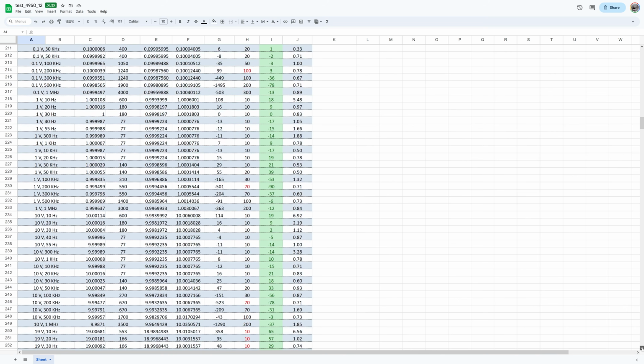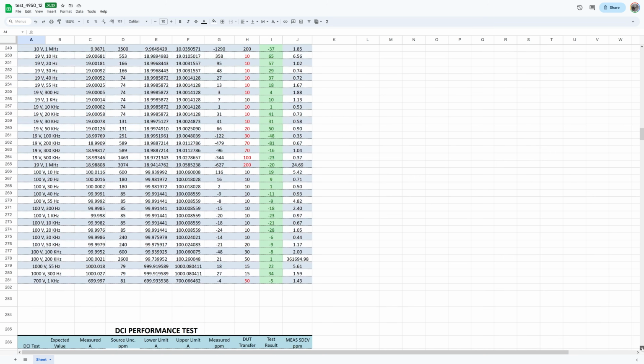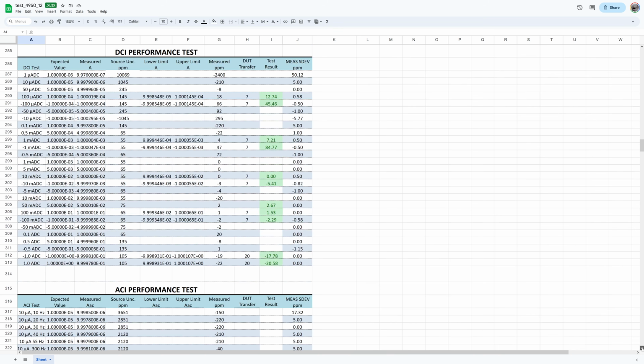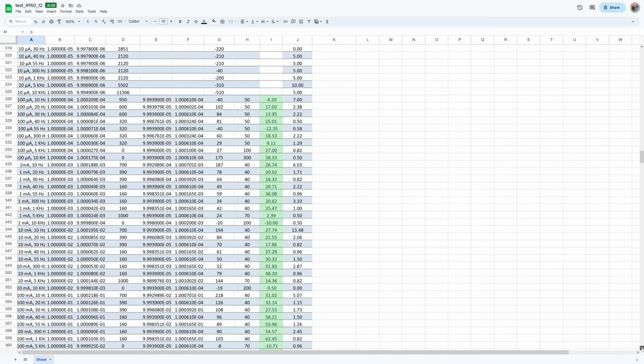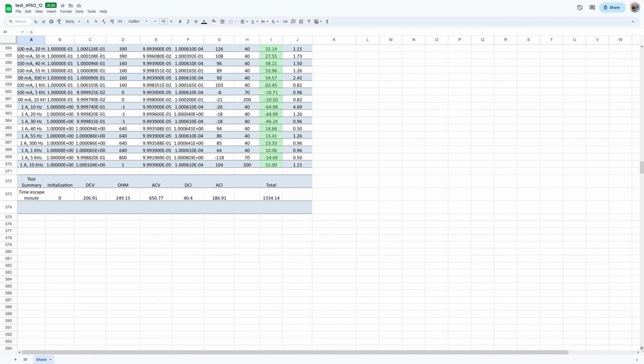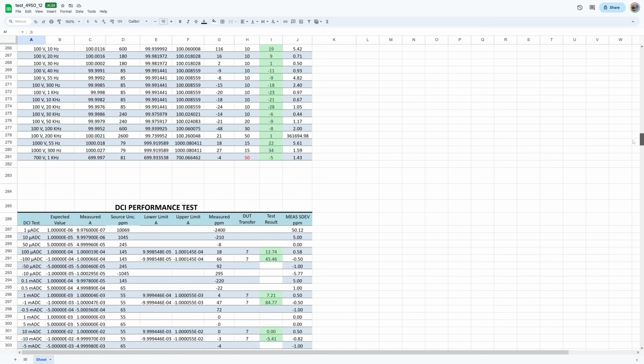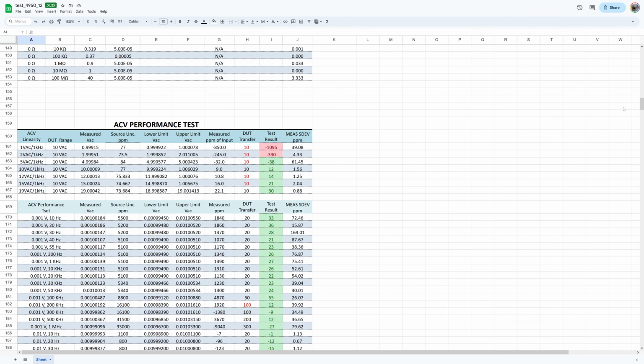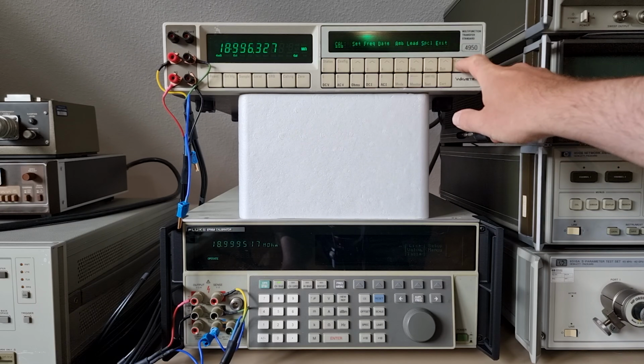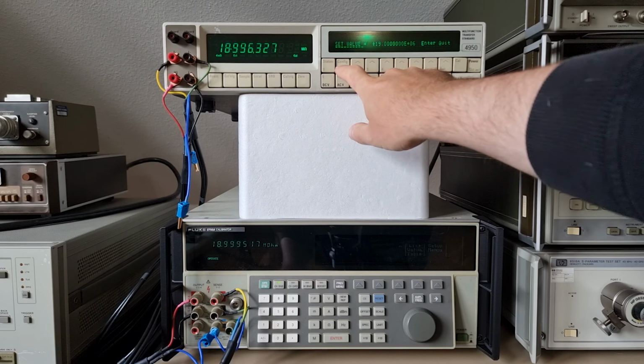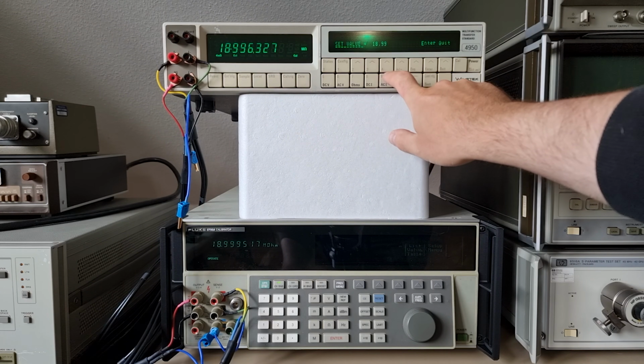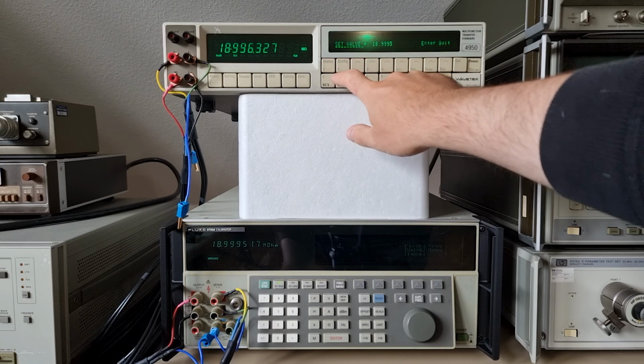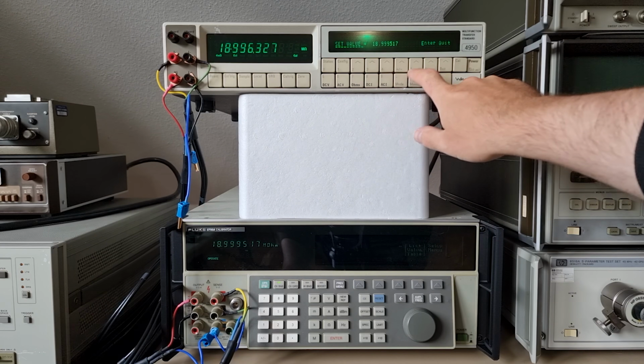It remains so for multiple runs across multiple days too, so I'm reasonably confident that I caught all the gross errors this time. Only the ACV linearity still seems to have a bit of a problem. Or it's the calibrator, which I also serviced myself and never really tested as extremely thoroughly as this. Linearity is not strictly necessary for our patient today. It's primarily meant to verify voltage at frequency points of interest with spot calibrations.